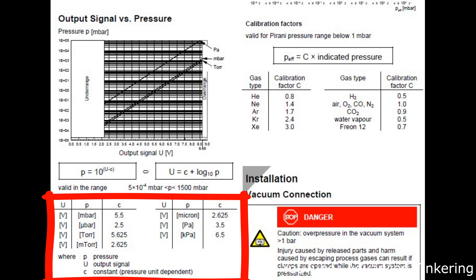This constant value determines the unit your pressure will be in. So for example, if you want your pressure in millibar you would use a C of 5.5. If you want your pressure in Torr you would use a C of 5.625.